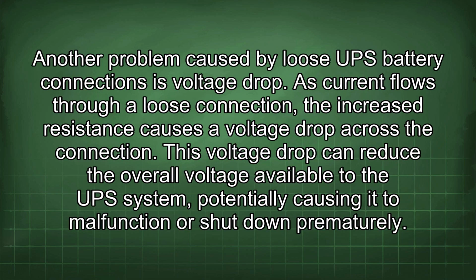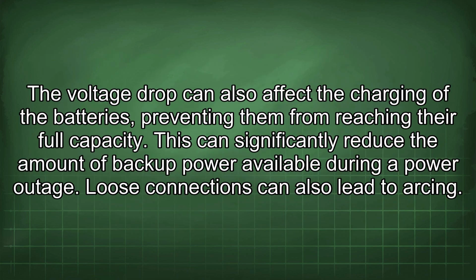Another problem caused by loose UPS battery connections is voltage drop. As current flows through a loose connection, the increased resistance causes a voltage drop across the connection. This voltage drop can reduce the overall voltage available to the UPS system, potentially causing it to malfunction or shut down prematurely. The voltage drop can also affect the charging of the batteries, preventing them from reaching their full capacity. This can significantly reduce the amount of backup power available during a power outage.